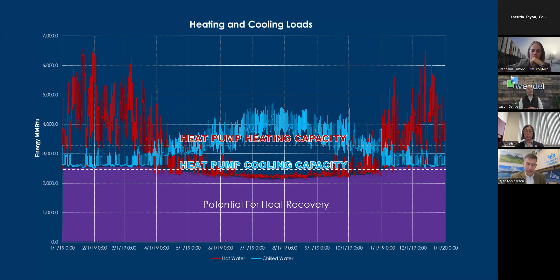Conversely, you may be using cooling for inside spaces like data centers in the middle of winter. That's another opportunity to recover energy. So we look for heat recovery heat pumps that straddle that simultaneous heating and cooling line, which can be implemented inside a building or group of buildings to recover energy from one system to another.